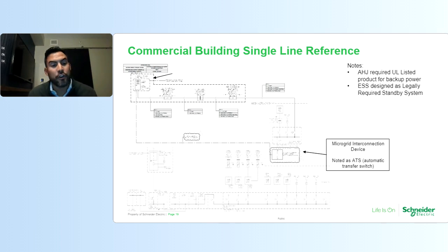So what the client wanted to do here was add an energy storage system to provide backup power to this elevator. And what was important for this facility, it was a legally required facility. So they wanted a UL listed product. And they wanted to use this energy storage system specifically for a legally required standby system. So here, they actually had the transfer switch installed.